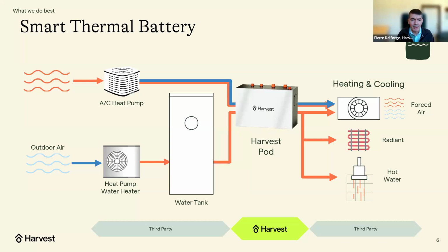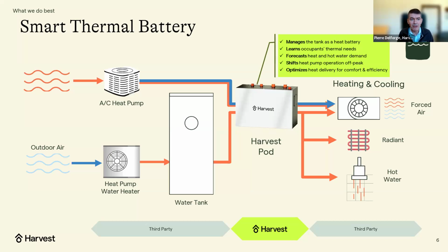So the key functions of the Harvest Pod are, one, to manage the thermal storage tank as a battery by monitoring state of charge, and basically optimizing when it is charged and making sure there's always enough hot water in the tank for occupants' heating needs and domestic hot water needs.